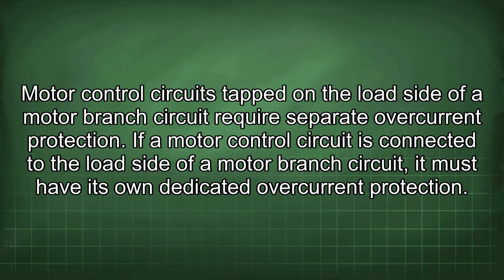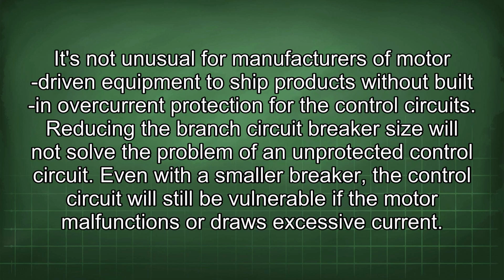Motor control circuits tapped on the load side of a motor branch circuit require separate overcurrent protection. If a motor control circuit is connected to the load side of a motor branch circuit, it must have its own dedicated overcurrent protection. It's not unusual for manufacturers of motor-driven equipment to ship products without built-in overcurrent protection for the control circuits. Reducing the branch circuit breaker size will not solve the problem of an unprotected control circuit. Even with a smaller breaker, the control circuit will still be vulnerable if the motor malfunctions or draws excessive current.